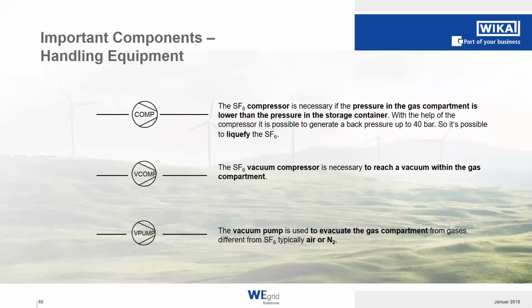Within the GPU, we have three main components. We have the SF6 compressor, which is necessary if the pressure in the gas compartment is lower than the pressure in the storage container. So if the pressure drops in the gas compartment, the SF6 compressor will generate a back pressure of up to 40 bar, and therefore push the gas into our storage tank within the unit. Or it also could transmit it through the unit into an external tank or the cylinders, for example.